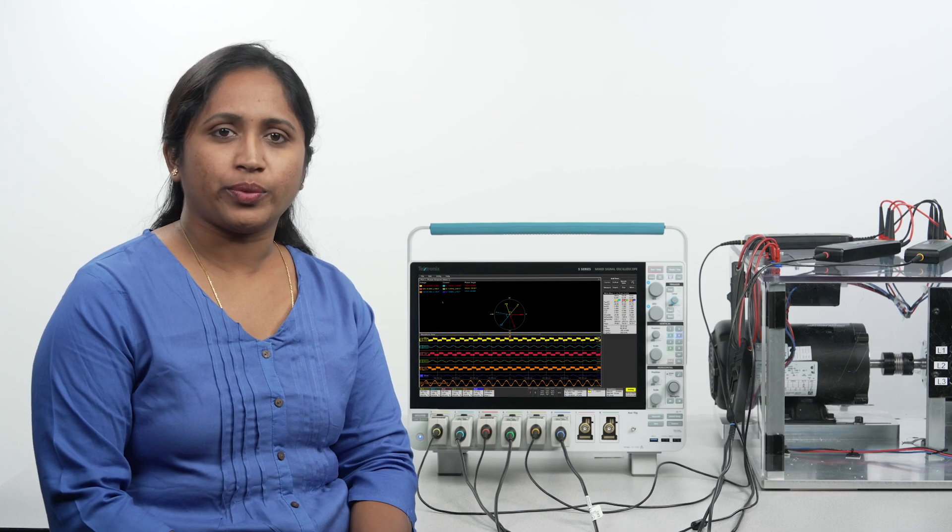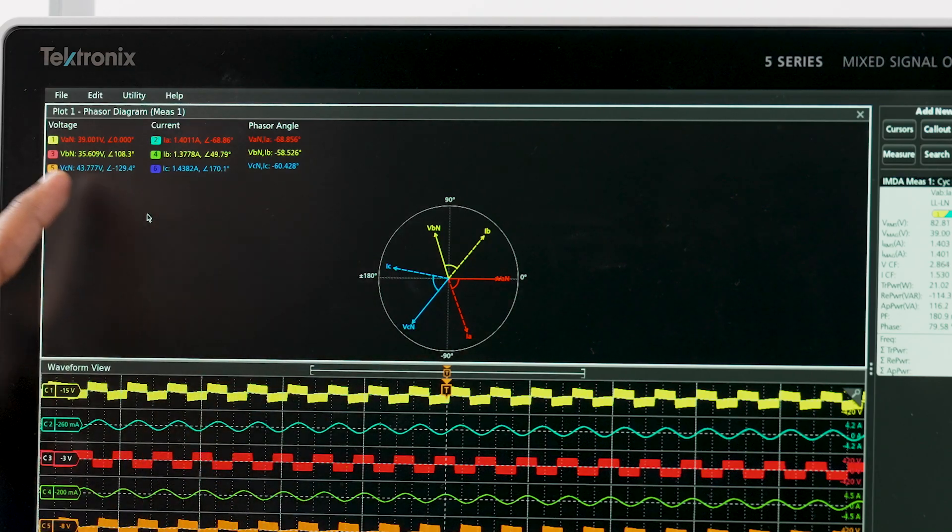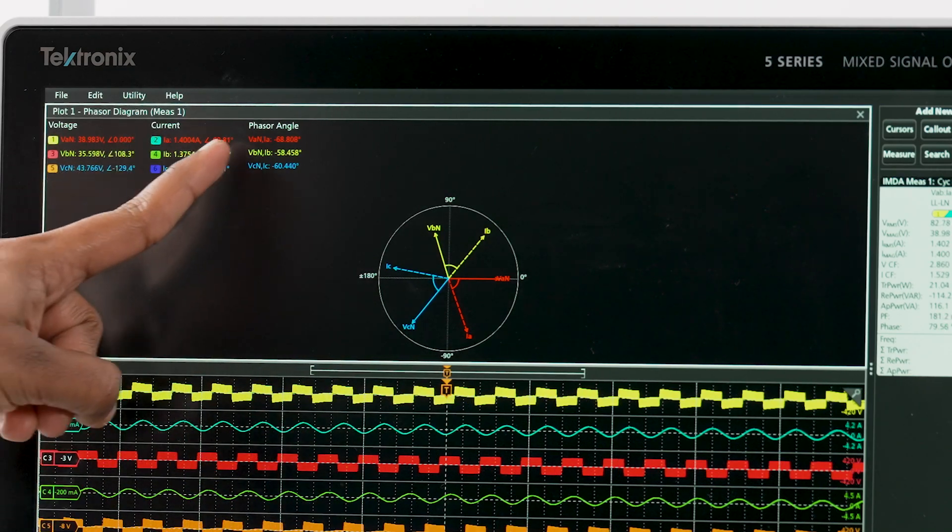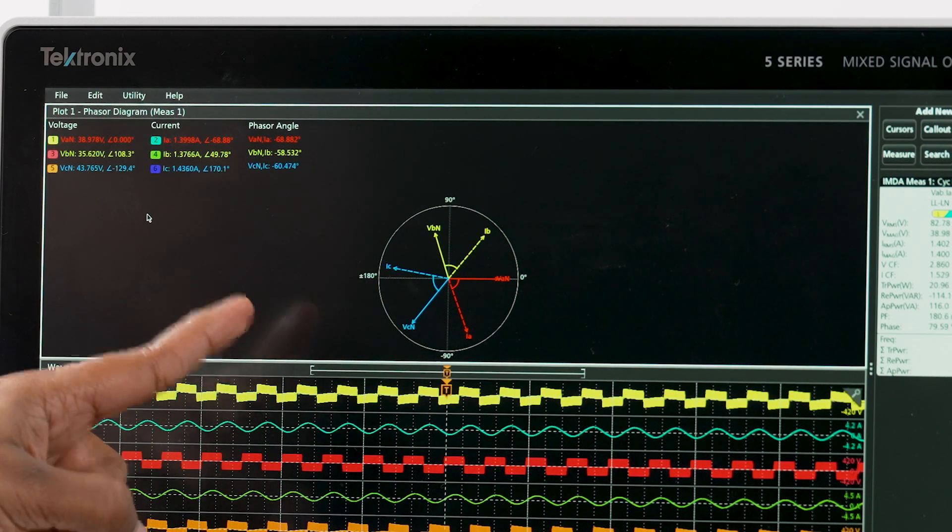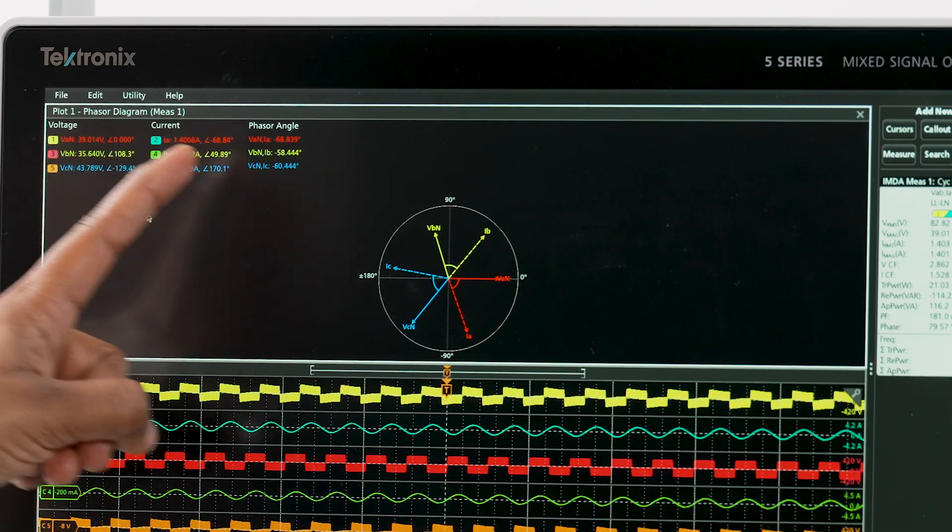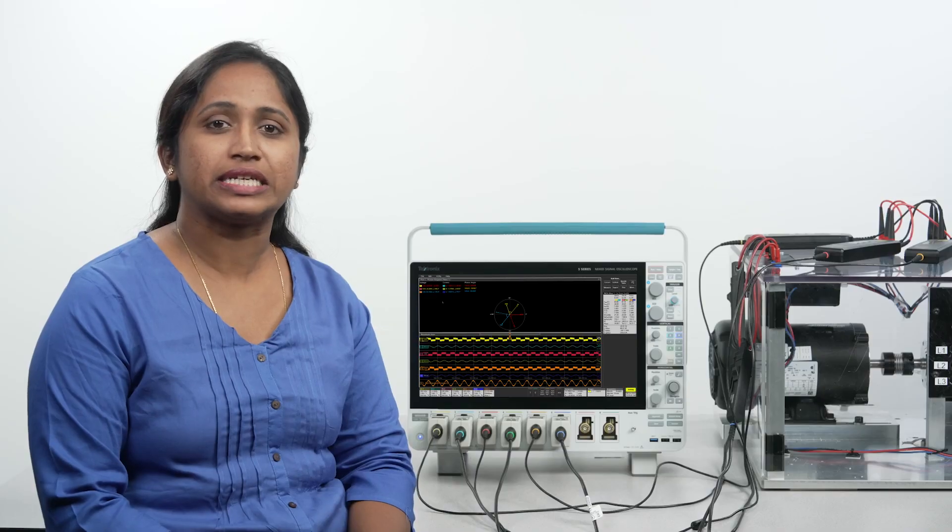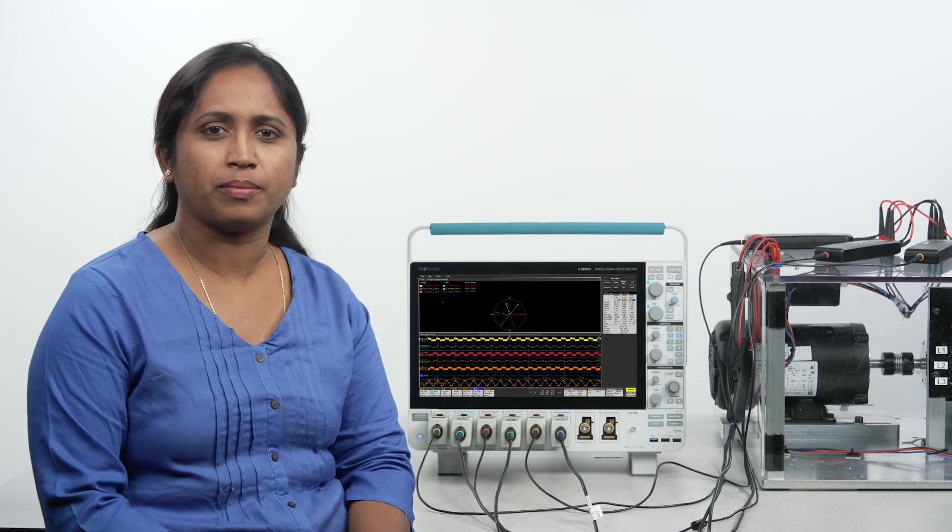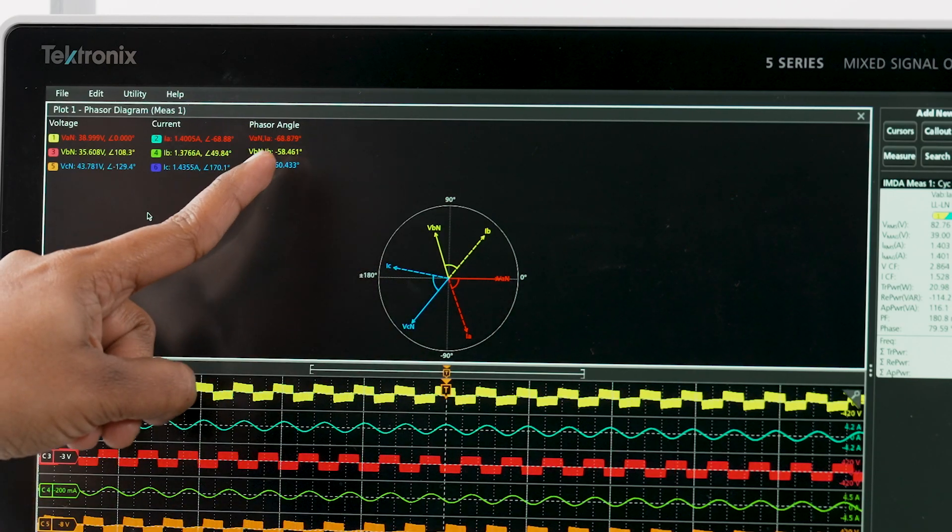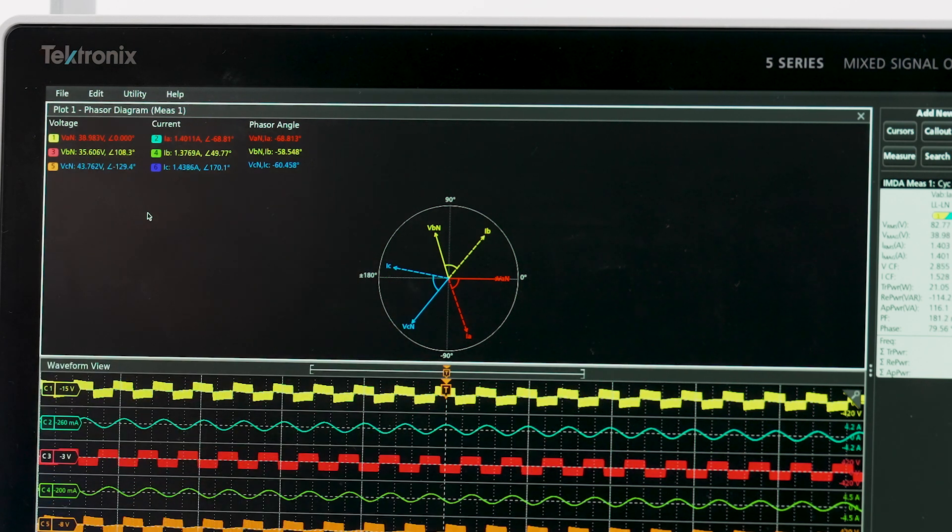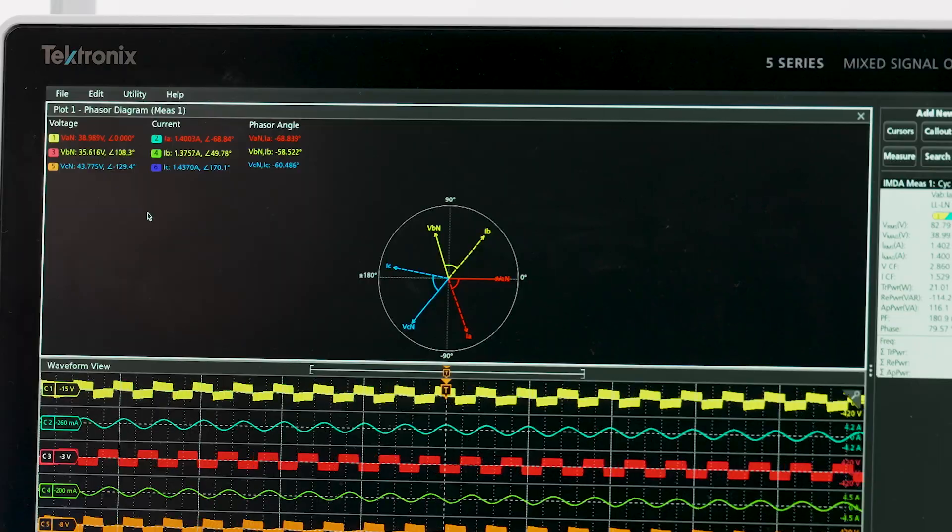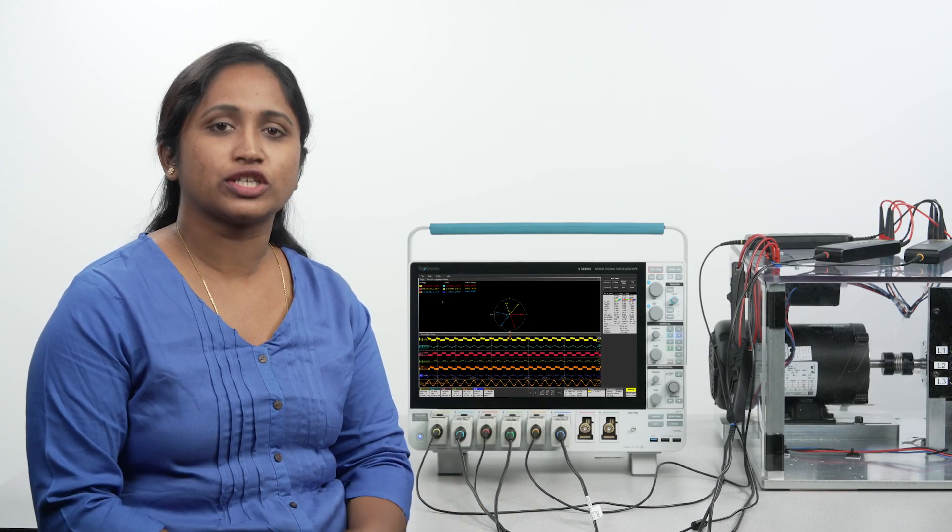Voltage and current vectors can be displayed on a phasor diagram, so you can quickly judge phase shift for each phase and the balance among phases. Each vector is represented by a magnitude value and phase is computed using the discrete Fourier transform method. As you can see, each voltage is leading the current by approximately 60 degrees, which is what I had expected for an inductive load. This gives me confidence that my wiring is good.